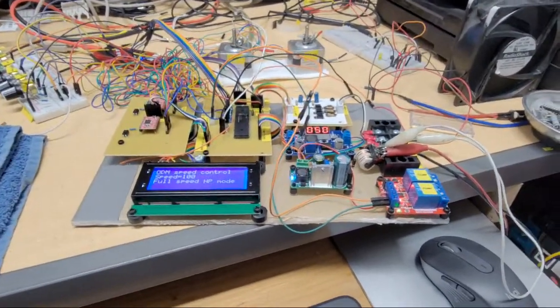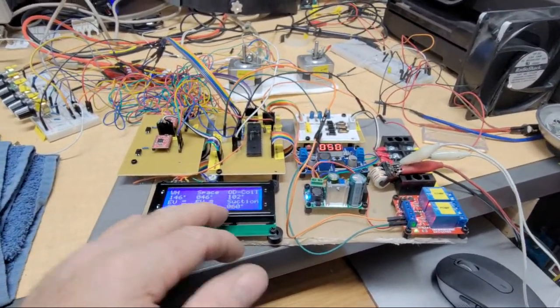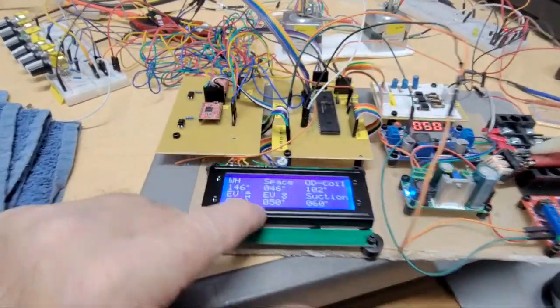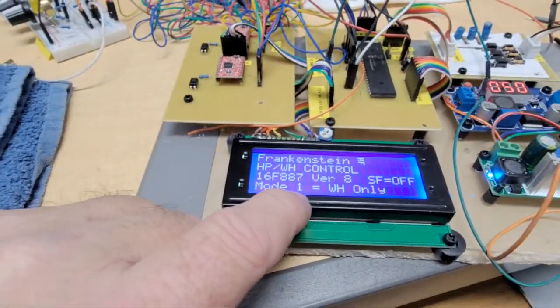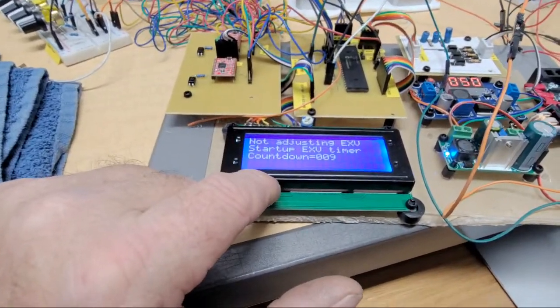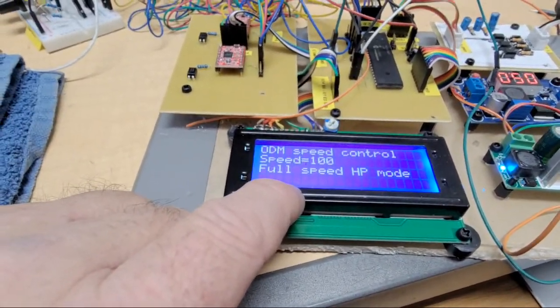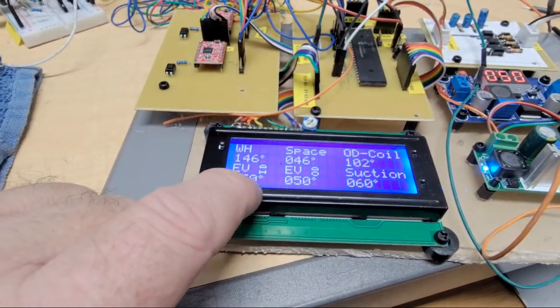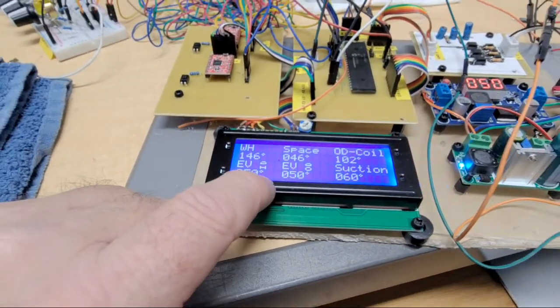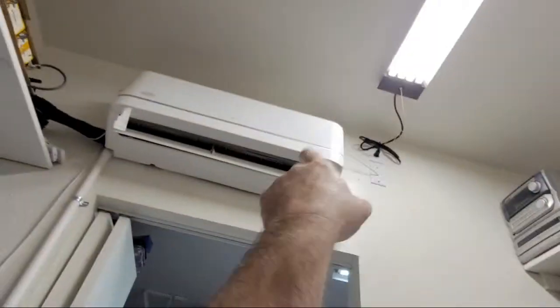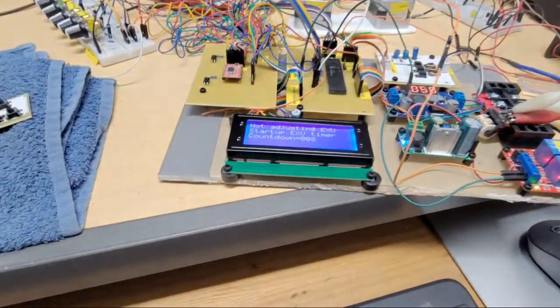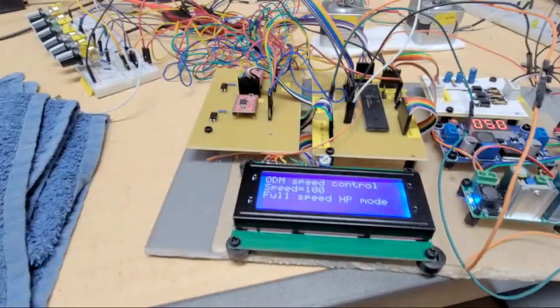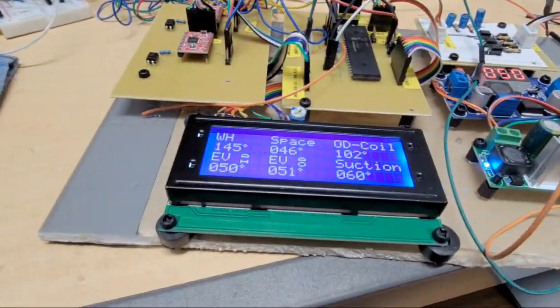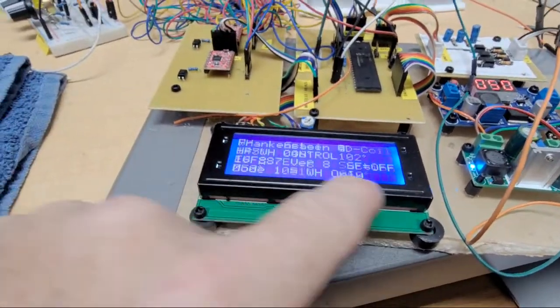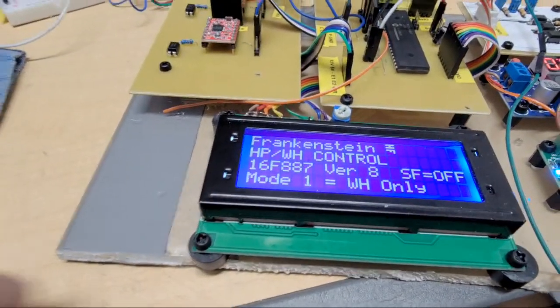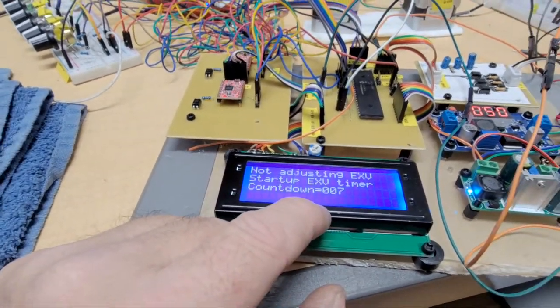Now, in water heater only, it'd be using the outdoor coil. I added a couple of custom little text characters out here just to see if I could do it. That's some sideways stuff. Look, ID, OD. So it's evaporator ID, OD: the inlet for that one's ID, and the inlet to the evaporator outside was the OD one, and then they had a common suction line. So to do superheat, you're just looking at your coil inside or outside, and then your suction, and that'd be a superheat. So right there it's probably around 9 or so, and then it would adjust once it had to.